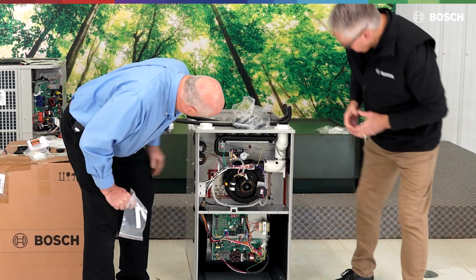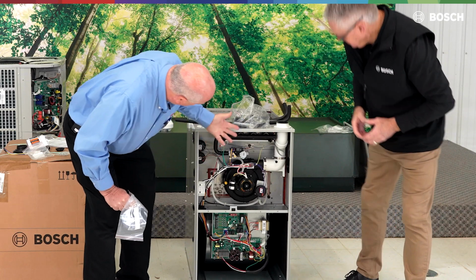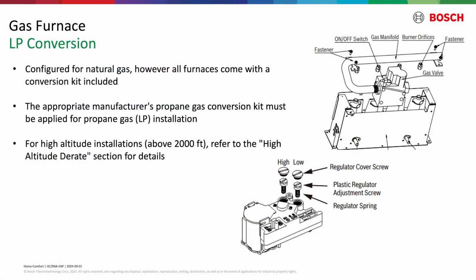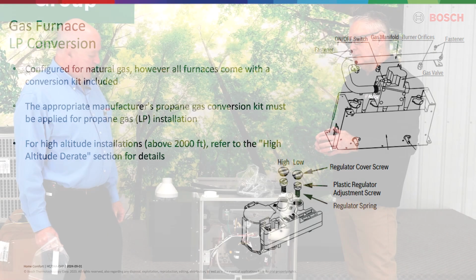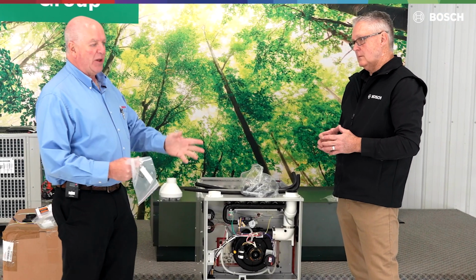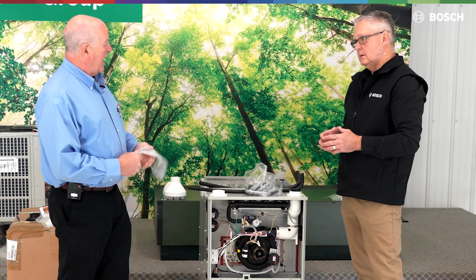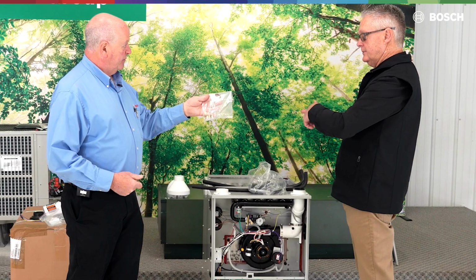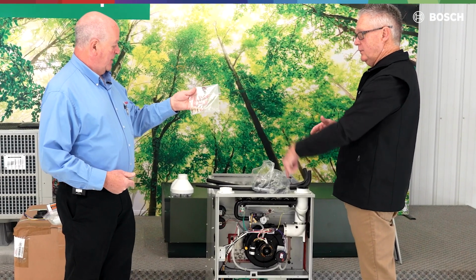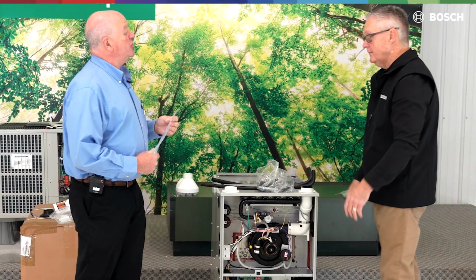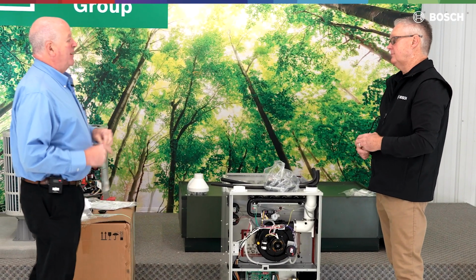We can usually pull these 4 screws here, roll the manifold back, change the 4 orifices, or 3. This is a 4 orifice, it's a 4 tube, and put it back in. You don't have to pull off all the wires and all the connections. You usually can roll them back if you have to. So I don't have to ask the distributor for the propane kit? That came with it. It came with it. Unless you're over 2,000 feet. And then we have to... Yeah, then we have to go that way.